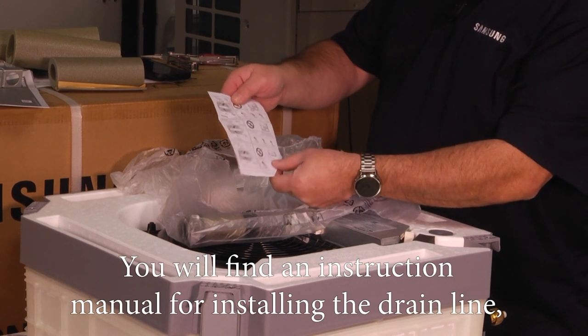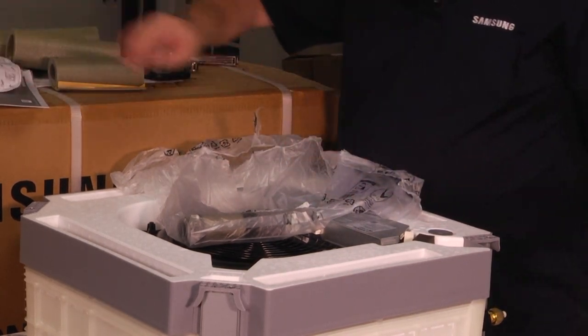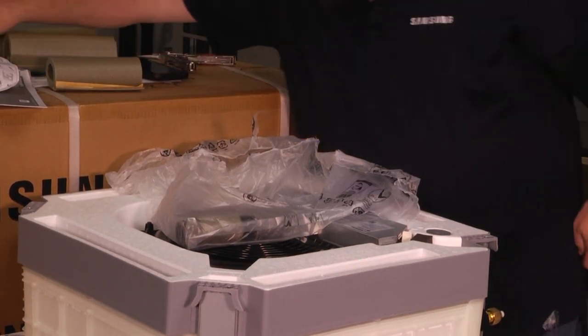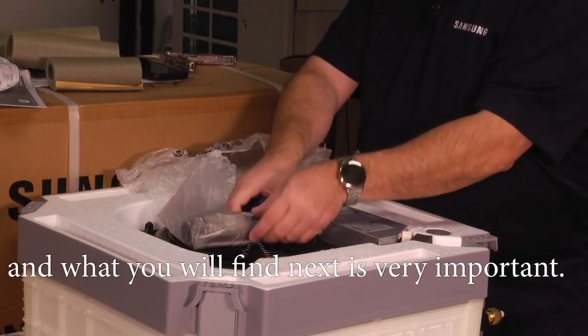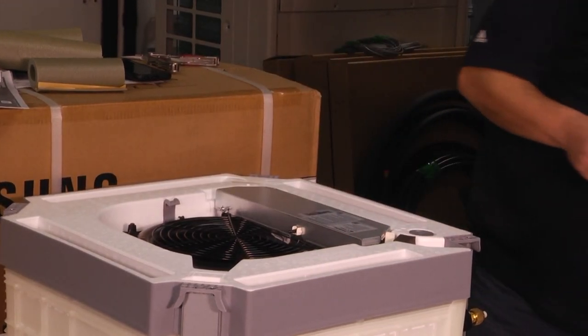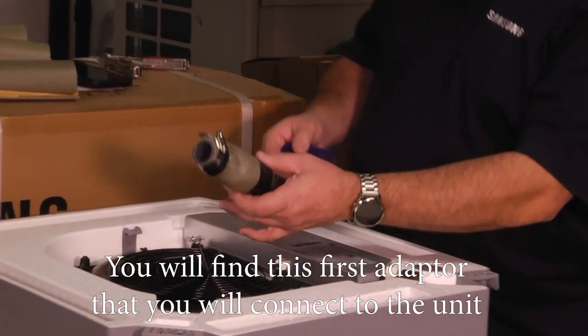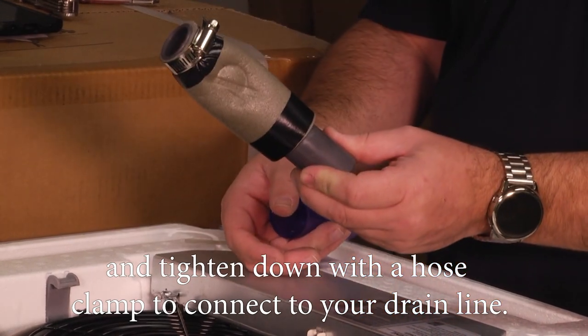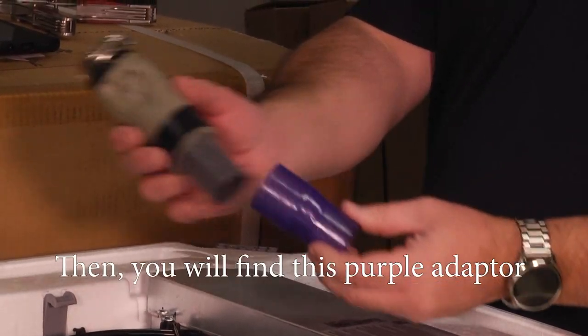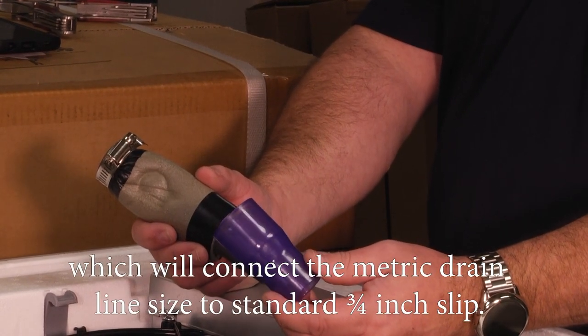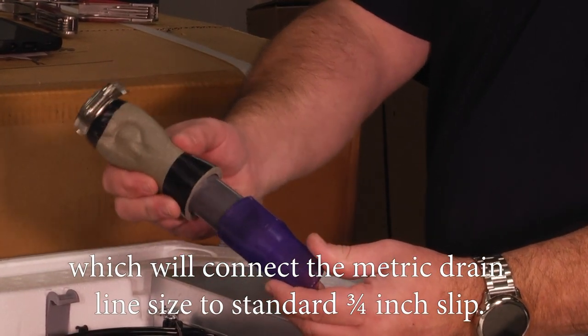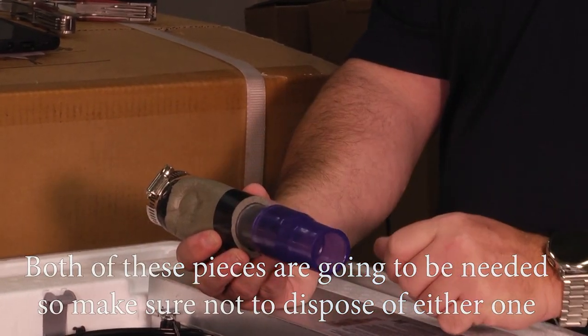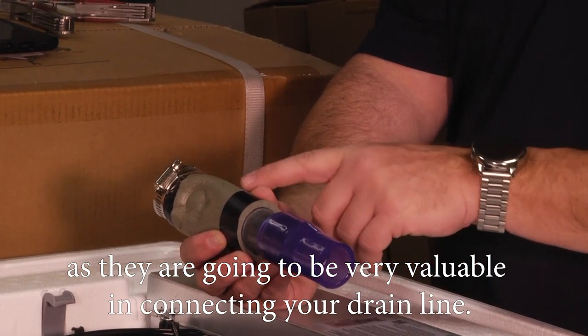You'll find an instruction manual for installing the drain line, some various zip ties to hold everything in place, and what you'll find next is very important. You'll find this first adapter that you will connect to the unit and tighten down with a hose clamp to connect to your drain line. Then you'll find this purple adapter which will convert the metric drain line size to standard three-quarter inch slip. Both of these pieces are going to be needed, so make sure not to dispose of either one.